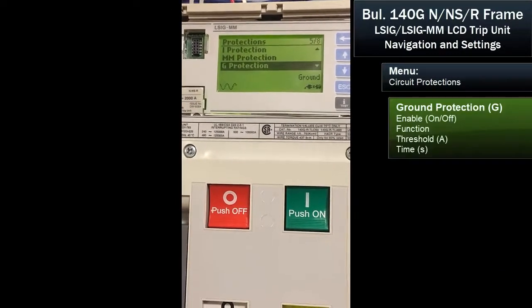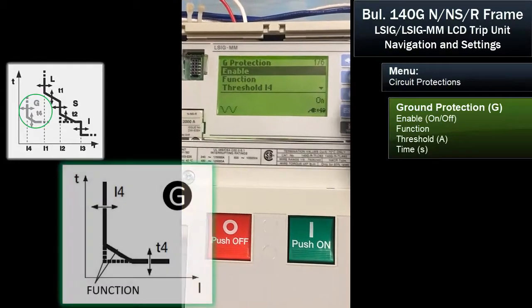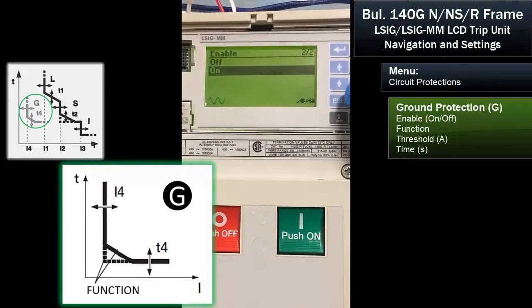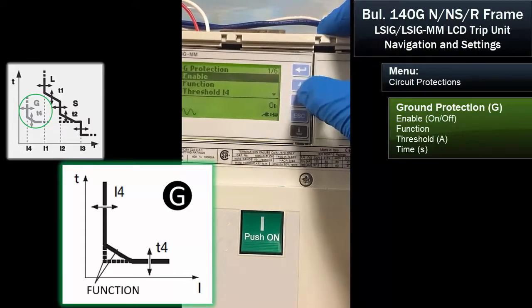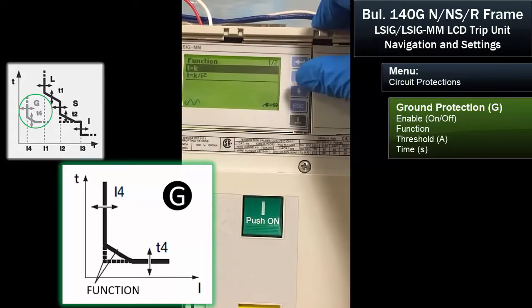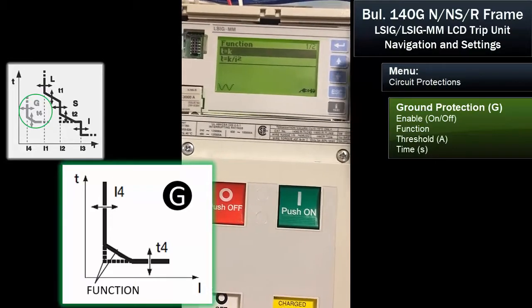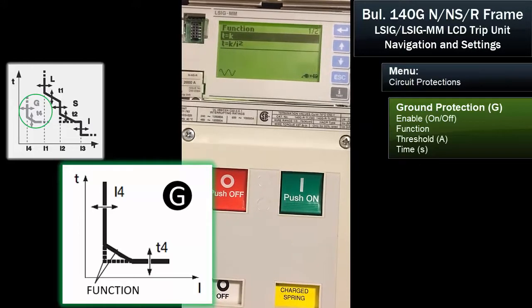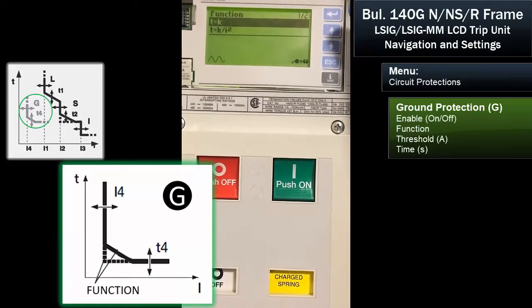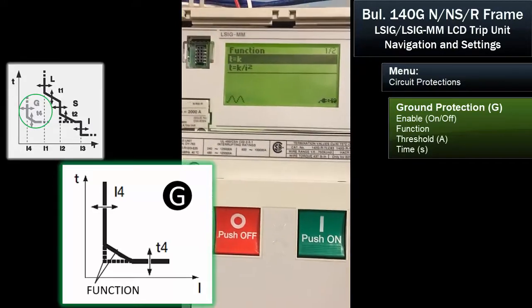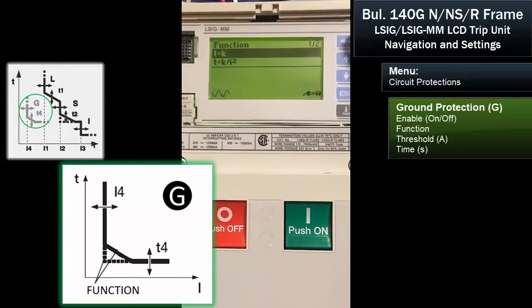Now I've scrolled to the ground protection. We're at ground protection. I've enabled it — it's enabled. Let's look at the function. This can be either instantaneous or a thermal response. The choice is up to you depending on what type of ground leakage or ground faults you may have. I'm going to leave it at a constant — many customers use it so that if ground current is above a set value, the breaker trips instantaneously. That's how this is set up, where T equals K.